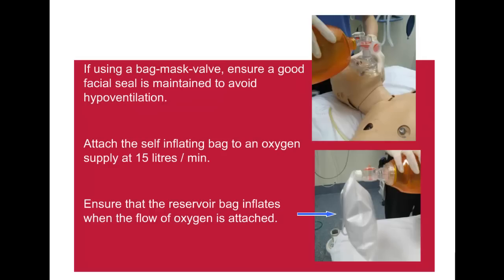The self-inflating bag can be connected to a face mask, tracheal tube or supraglottic airway device. On squeezing the bag, its contents are delivered to the patient and on expiration diverted to the atmosphere; the bag then refills automatically. If the self-inflating bag is not connected to an oxygen supply, the percentage of oxygen delivered will be 21%. When high flow oxygen is connected directly without a reservoir, oxygen percentage rises to 45%. An inspired oxygen concentration of approximately 85% is achieved if a reservoir system is attached and oxygen is delivered at maximum rate. Ensure that the reservoir bag expands when oxygen is attached and check the integrity of the self-inflating bag and reservoir.